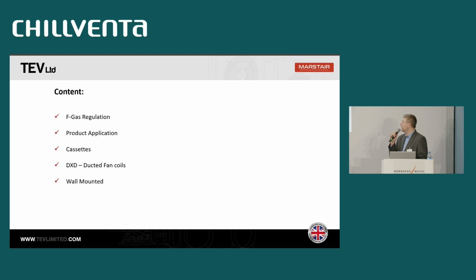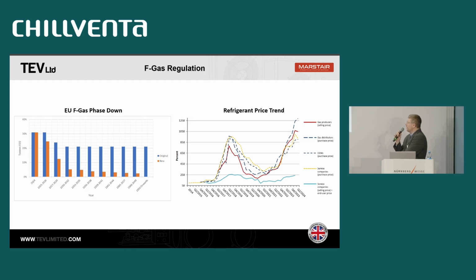Okay, so briefly on the F-gas regulation. We've probably seen this graph or a similar graph a million times before, of what the original F-gas phase down was and what the new F-gas phase down is. And basically, there's a very, very sharp phase down. So if you're still using the old A1 refrigerants, there needs to be a move to start thinking about either the A2Ls or CO2 or some sort of alternative.